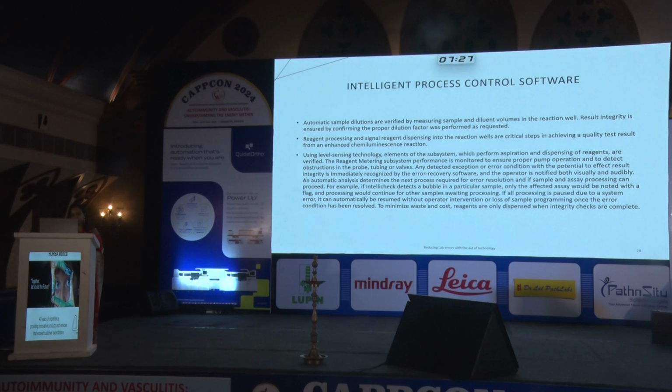Reagent processing and signal reagent dispensing into the reaction well are critical steps in achieving quality test result from an enhanced chemiluminescent reaction, which is again very important for measurement of different immunoassay parameters. Using level sensing technology, elements of the subsystem which perform aspiration and dispensing of the reagents are verified.